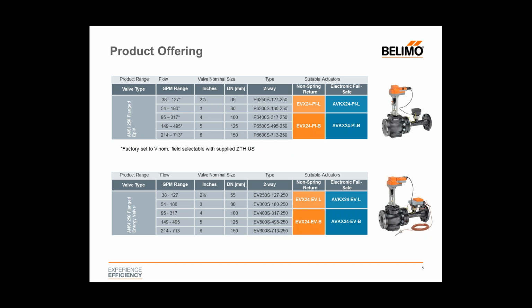The way these valves are configured is they are shipped from our factory configured at what's called VNOM, the highest capacity flow rate of the valve. And then the valve can be set all the way down to 30% of VNOM. So in the case of the 2.5 inch, it can be set all the way down to 38 GPM. Now what we provide with each unit that ships is what's called a ZTHUS, which is a handheld field programmable device. What that allows you to do is set the flow in the field for each unit. So it provides a very flexible way.